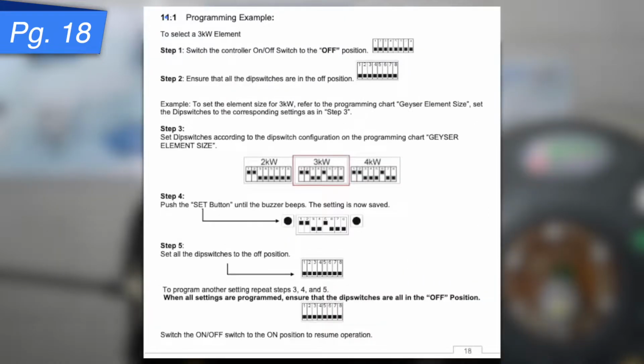So if you look at 14.1, to select a 3 kilowatt element, switch the controller on or off switch to the off position. So remember, you're making any changes with dip switches, toggle off. Then ensure all the dip switches are in the off position, which is all down. To set the element size for a 3 kilowatt, just remember that that is the default setting, but if you want to change it, you'll see the other settings.